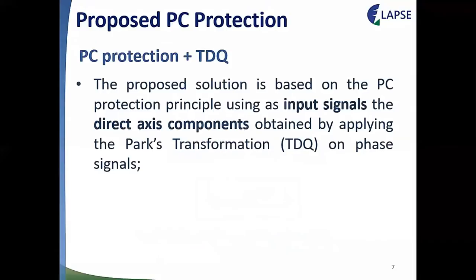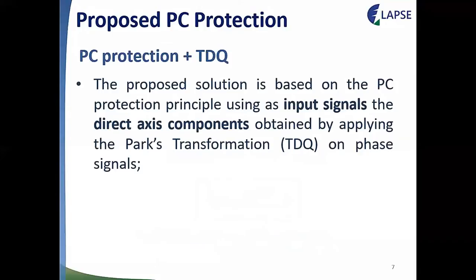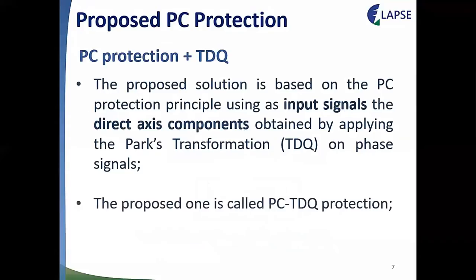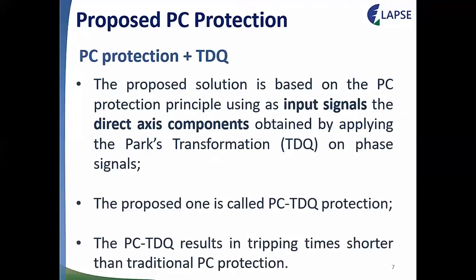Regarding the proposed PC protection: the proposed solution is based on PC protection principles using as input signals the direct-axis components obtained by applying the Park's transformation, the TDQ, to the phase signals. The proposed method is called PC-TDQ protection and results in tripping times shorter than traditional PC protection.